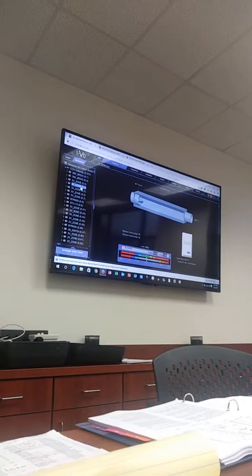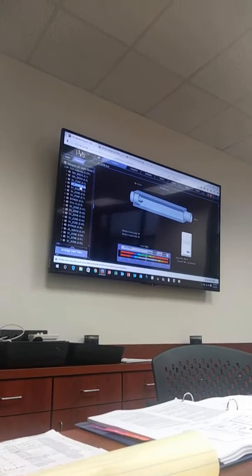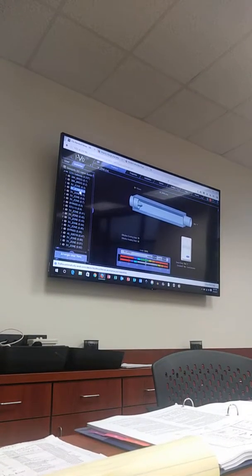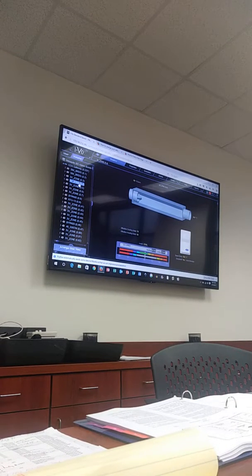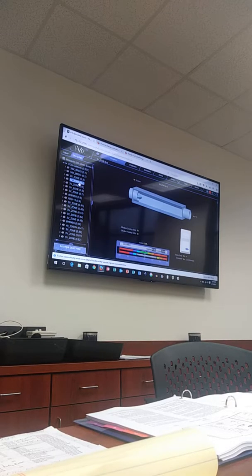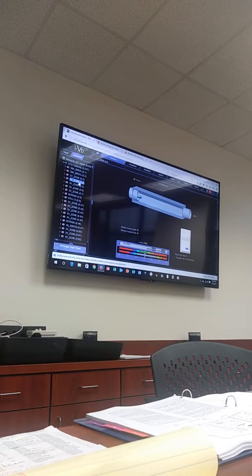Well, what we did, the main damper, we did close it down so it doesn't open up. But when the zone calls, the manual balancing damper and the 16-inch damper, we set the set point where it doesn't open up 100%. Right, so the set points will make it go to minimum if it's not calling, but we also need to set the minimum damper position to 0. Can't we shut them? Don't we have to have 200 CFM or something?